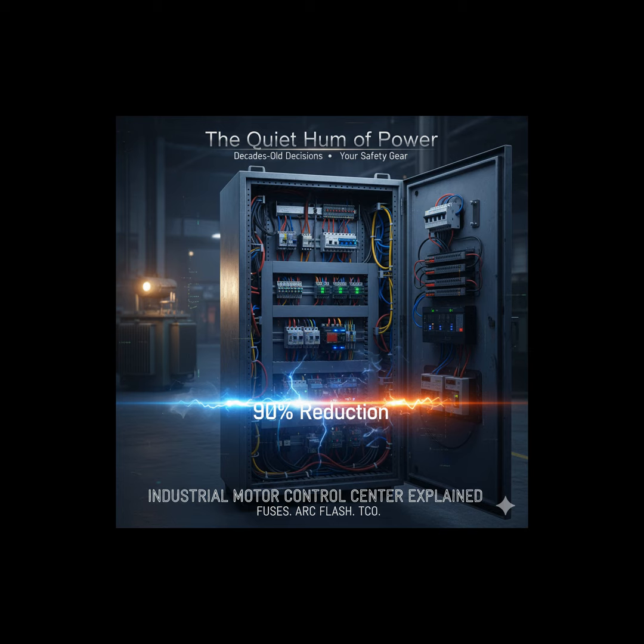electrical facility: arc flash protection. This is the number one differentiator, and it is absolutely non-negotiable from a safety perspective. When a short circuit happens, that delayed clearing of a standard breaker can allow a massive, dangerous arc flash to occur. And the data backs this up. It does. Studies by IEEE and others have confirmed that current-limiting fuses can reduce the arc flash incident energy by up to 90% compared to standard breakers installed in the same environment. That is a huge number.